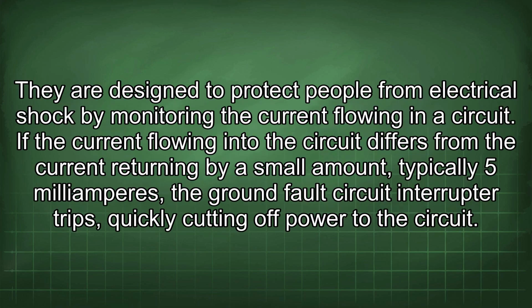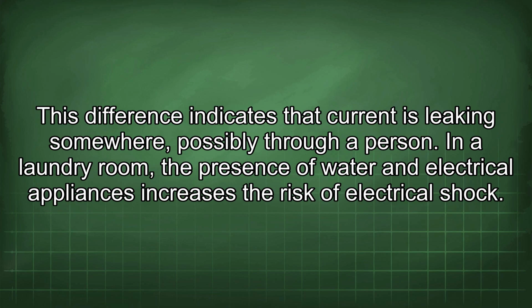They are designed to protect people from electrical shock by monitoring the current flowing in a circuit. If the current flowing into the circuit differs from the current returning by a small amount, typically 5 mA, the ground fault circuit interrupter trips, quickly cutting off power to the circuit. This difference indicates that current is leaking somewhere, possibly through a person.